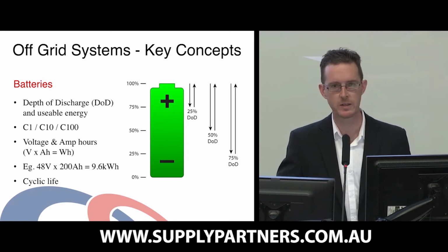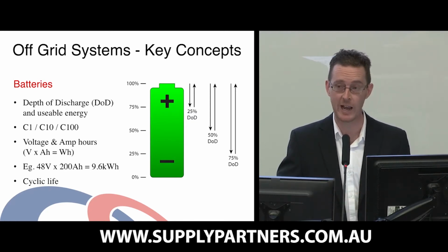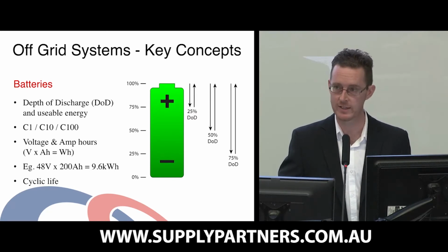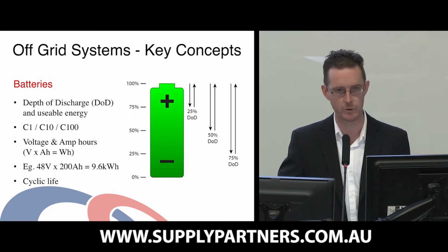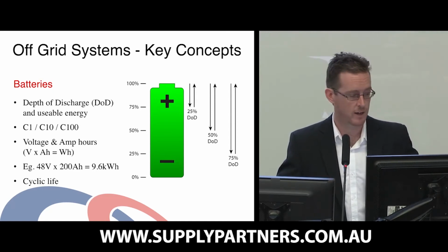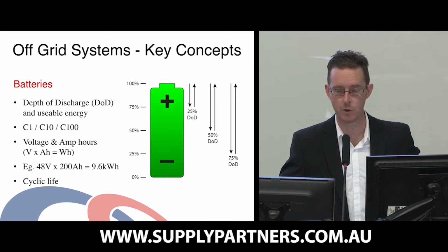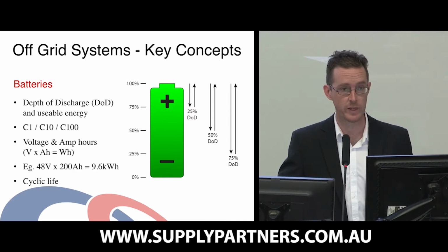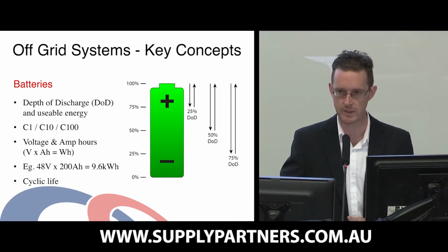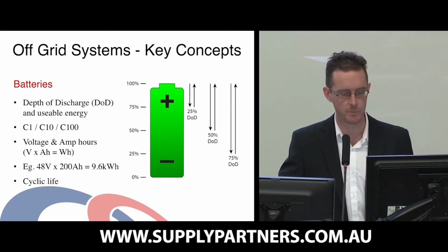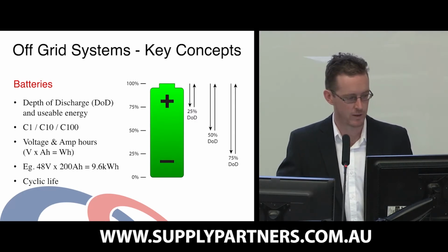So C100 means discharging the battery over 100 hours. That may not be realistic in day-to-day use, but C100 is a number you'll find commonly on battery data sheets, so it's important to understand what that is. C10, I think, is a better number to base your calculations on, but the amount of energy you can expect to get out of a battery in 10 hours is less than what you'd get out in 100 hours. C1 is something that was never really around in the days before lithium batteries, but we do see it popping up now with lithium batteries.